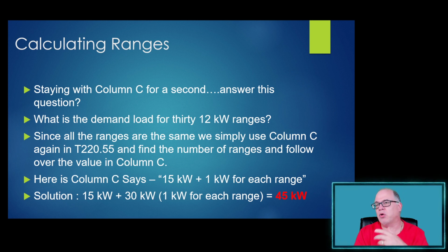So when I'm doing the load calculation under the standard method, and I have 30 ranges in my overall load calculation for that multifamily building, if I'm using the standard method here, then the contribution for that range load is what? 45 kW, and I simply add that into my equation, okay? Now, we're going to cover all this in my multifamily dwelling video, where I plug in some of these examples. But again, to be honest with you, when it comes to ranges, it's really just that simple, right? All right, let's do a little more. Let's get a little more complicated.